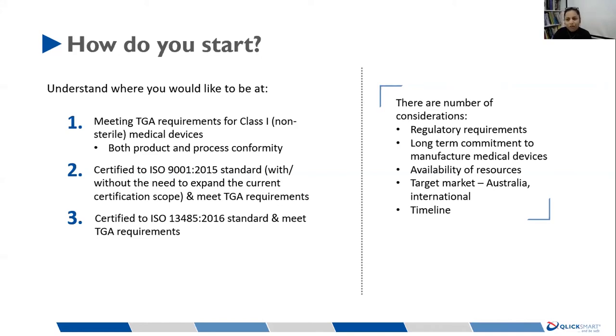You also have to identify your target market. Are you looking to supply only within Australia or supply internationally? And again, for example, TGA does not require quality management system certifications such as to an ISO standard for Class 1 non-sterile medical devices. But having that ISO certification may help fast track market entry in another country.